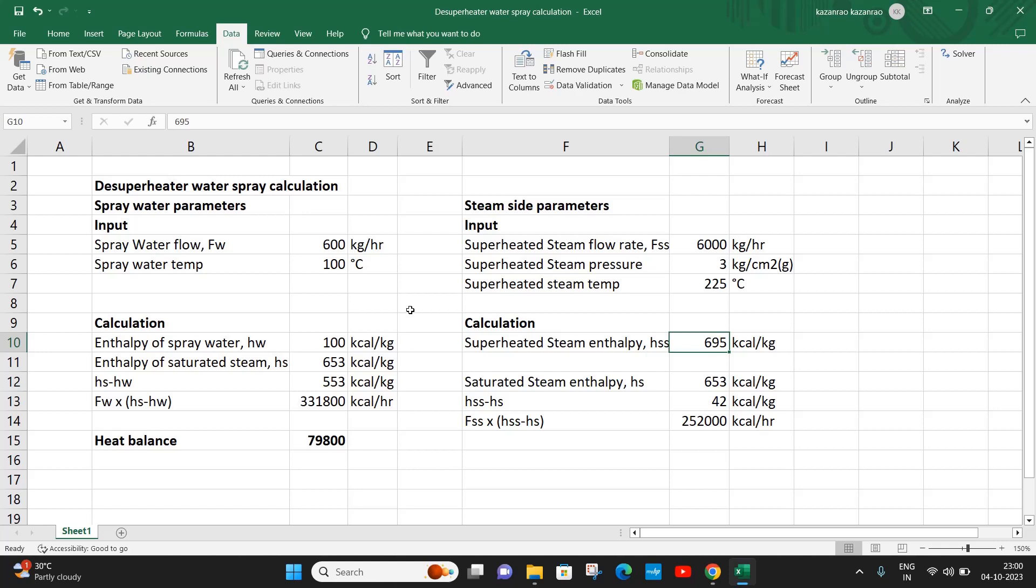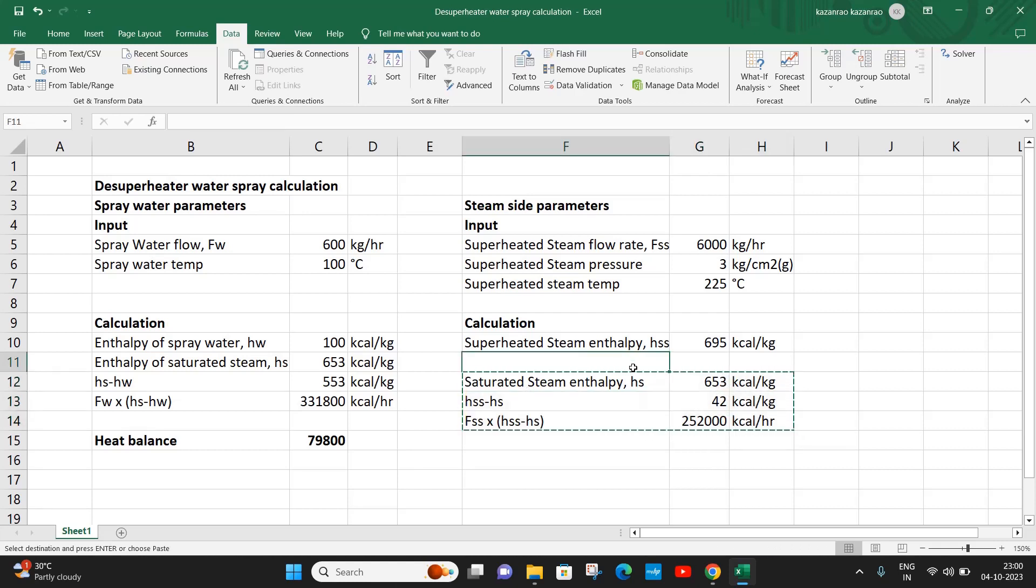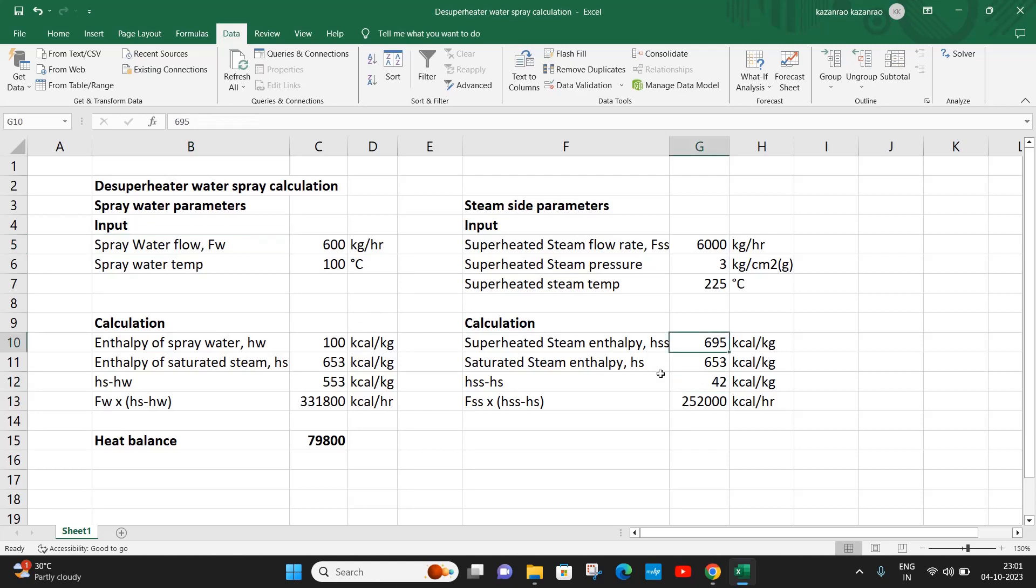And the enthalpy of saturated steam is 653 kilocalorie per kg. Now, our purpose is to calculate how much water has to be sprayed into this superheated steam pipeline so as to reduce the enthalpy from 695 to 653 when the superheated steam becomes saturated steam.